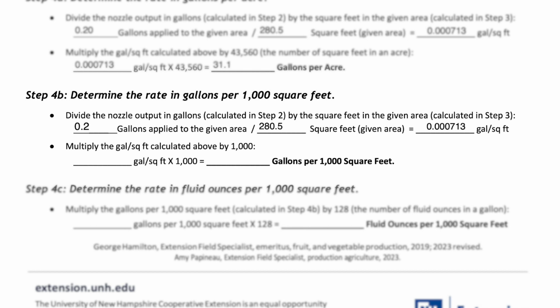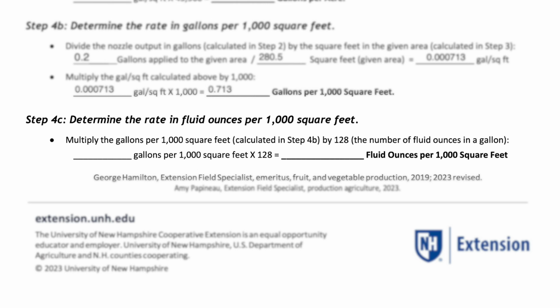We can also easily convert that application rate to a coverage area of 1,000 square feet. Take the 0.000713 gallons per square foot and multiply that by 1,000 for a total of 0.713 gallons per 1,000 square feet application rate. Now, let's take that 0.713 gallons per 1,000 square feet and multiply that by 128 to arrive at 91.3 fluid ounces per 1,000 square feet.